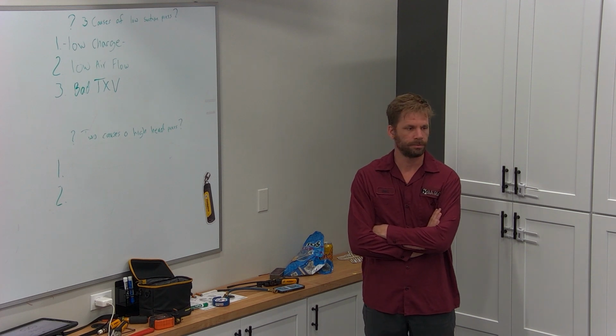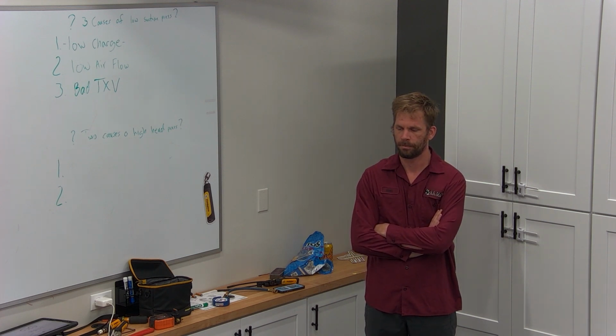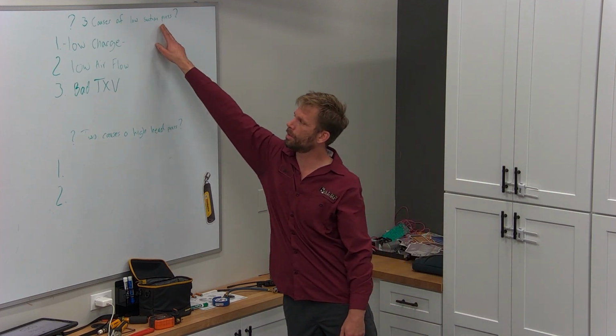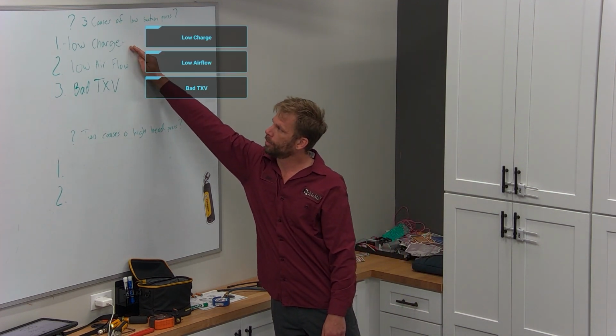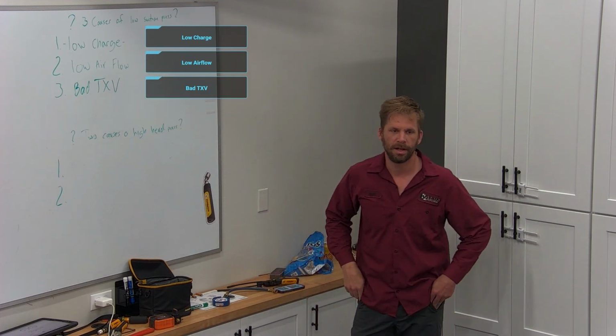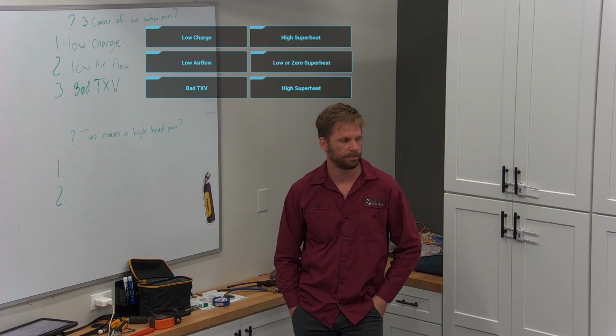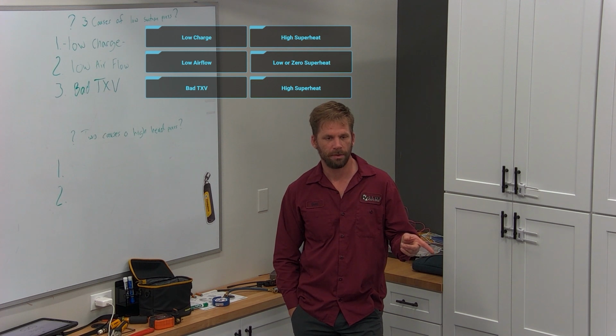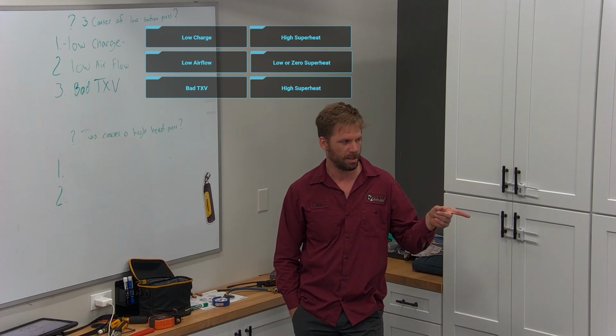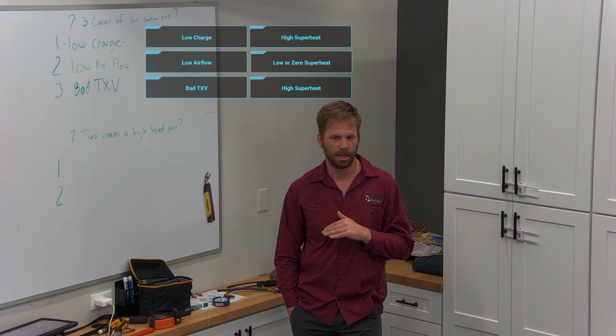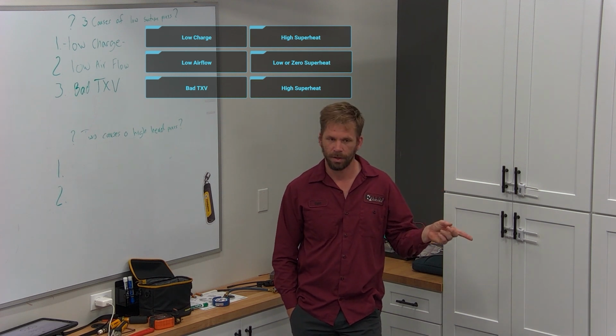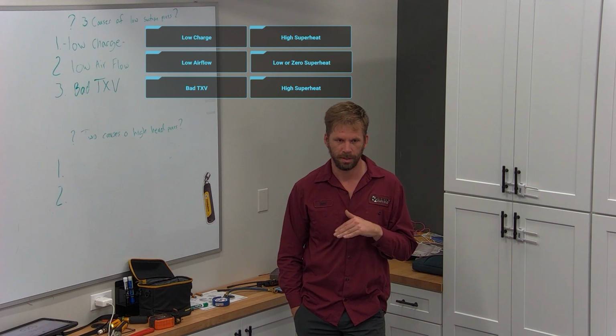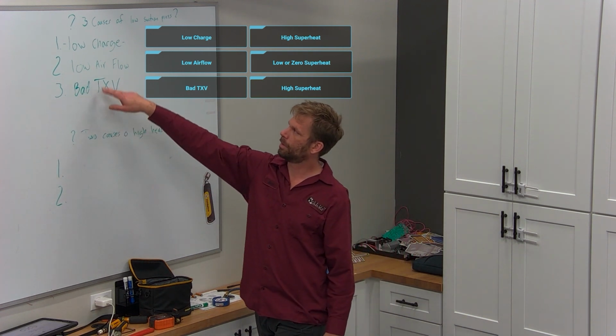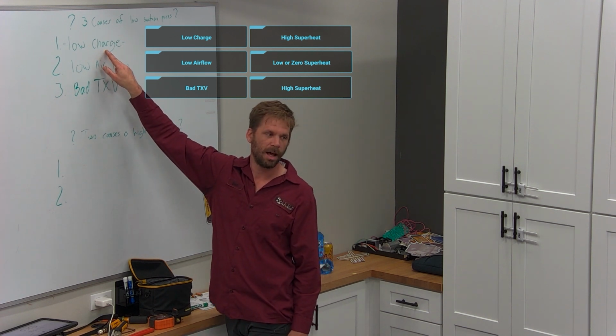Think about what Elliot did. He just created low airflow when he took the panels off. What happened? Your saturation dropped, which will be low suction pressure. So we already know all three of these have that. But low charge and bad TXV have something that airflow does not: superheat. Yep, it is superheat. Low or zero superheat. If you have a cold suction line, remember that's what happened immediately when you opened it? Cold suction line, you're going to have really low superheat. If it's bad airflow, it's not picking up as much heat, so low superheat. If it's being starved or low on charge, you're still picking up plenty of heat, so high superheat.